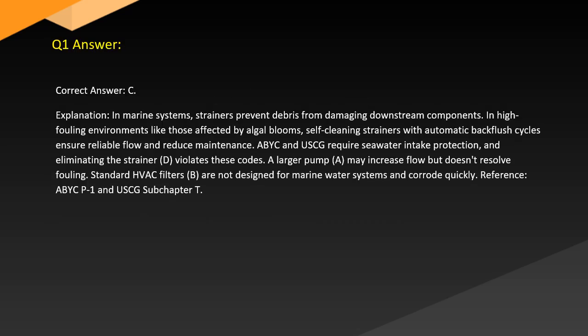Answer. Correct answer: C. Explanation. In marine systems, strainers prevent debris from damaging downstream components. In high-fouling environments like those affected by algal blooms, self-cleaning strainers with automatic backflush cycles ensure reliable flow and reduce maintenance. ABYC requires seawater intake protection, and eliminating the strainer, D, violates these codes.